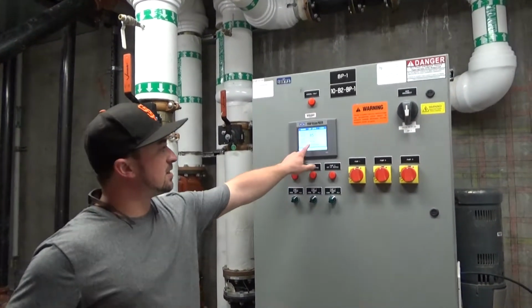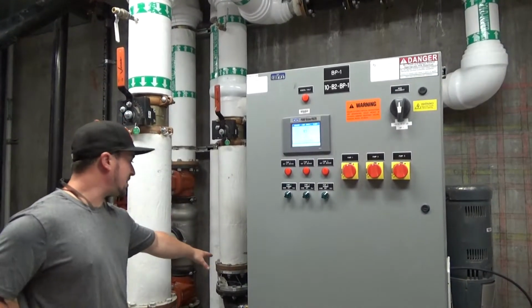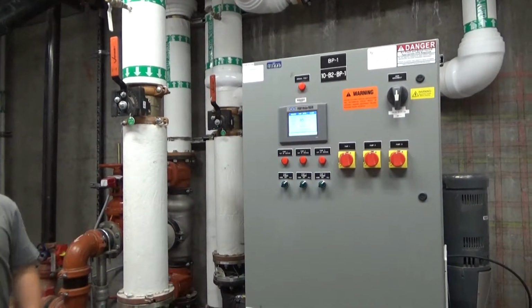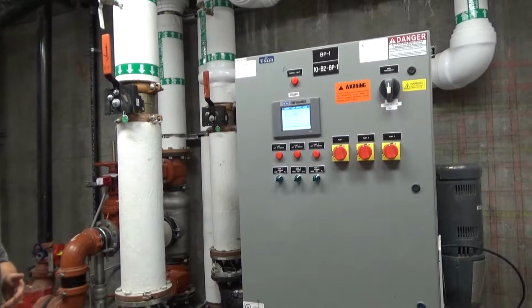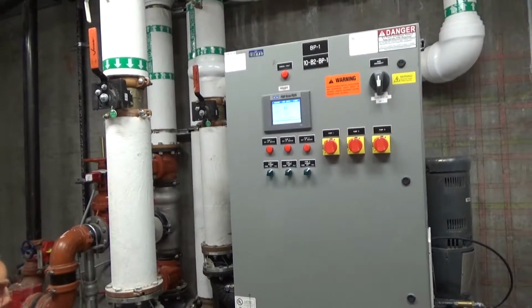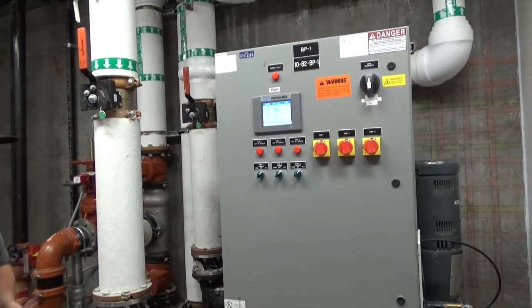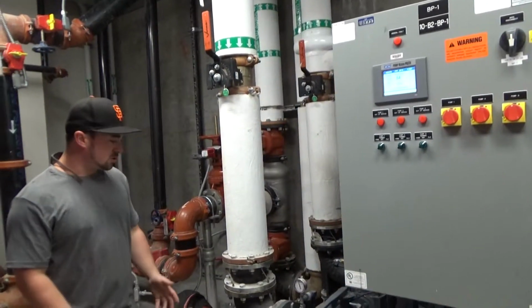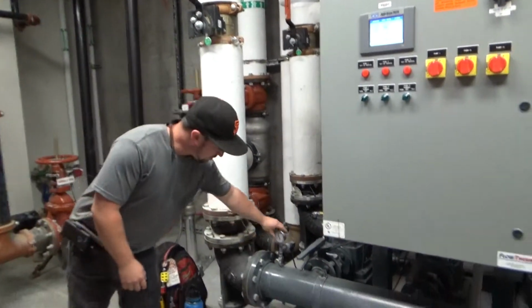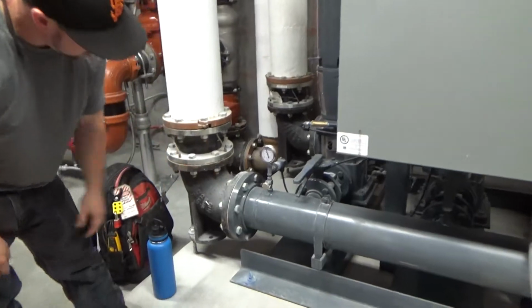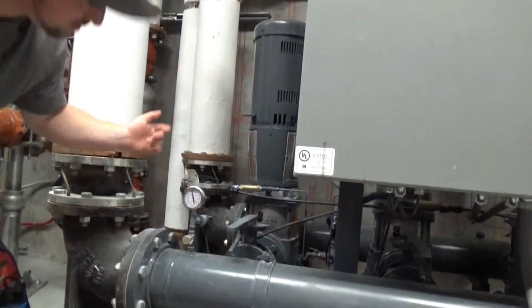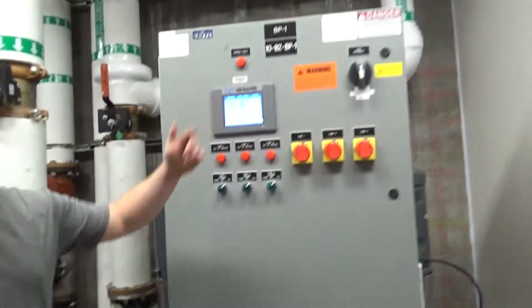City water, yeah, is 85 psi. And you also have a gauge on there that's going to tell you the same thing. Just to jump ahead, part of your preventative maintenance, or just one of your checks, is you want to come by every year or so and look at your gauge. So you've got your discharge gauge right here. My discharge gauge says 85 PSI. Make sure you have 85 PSI.